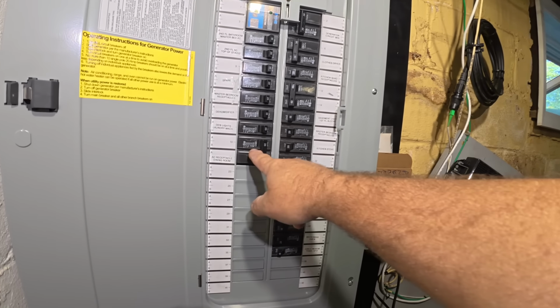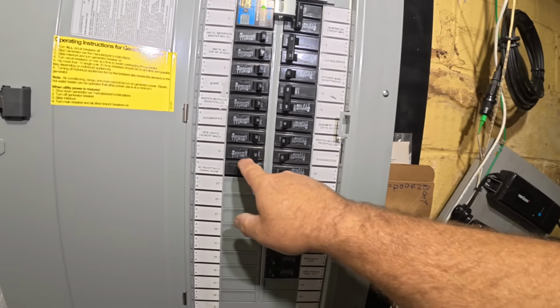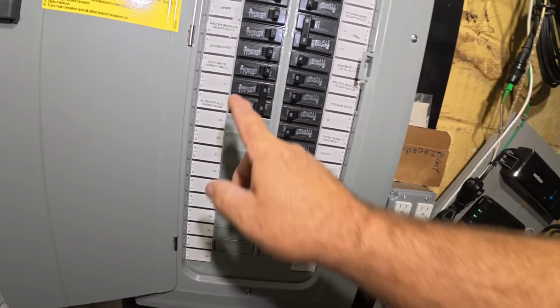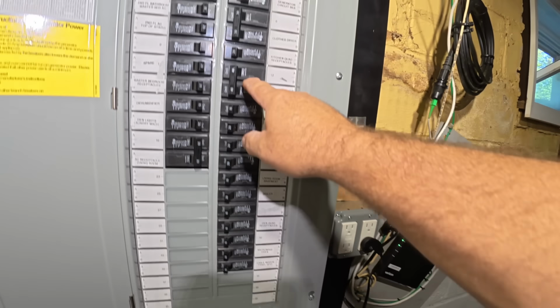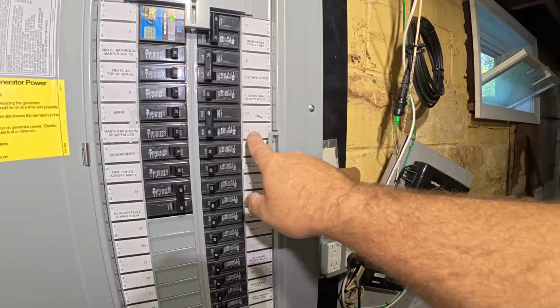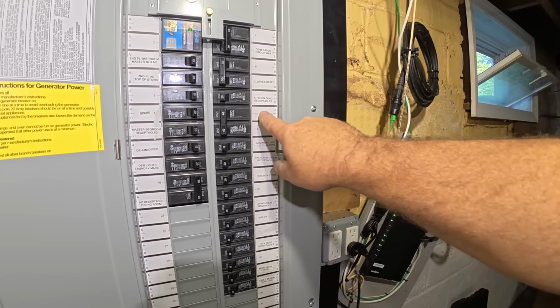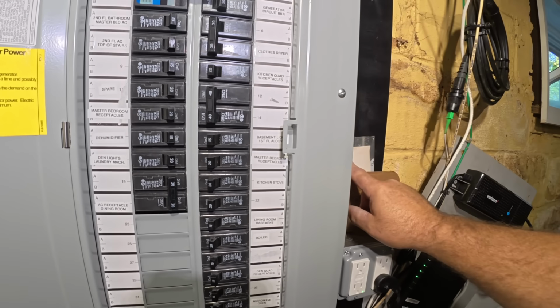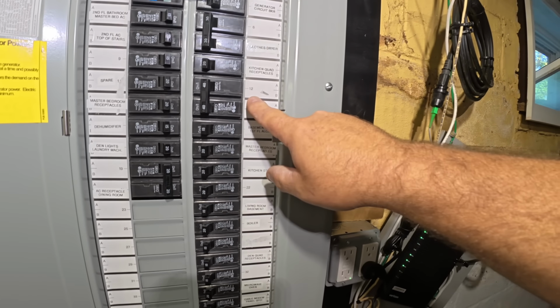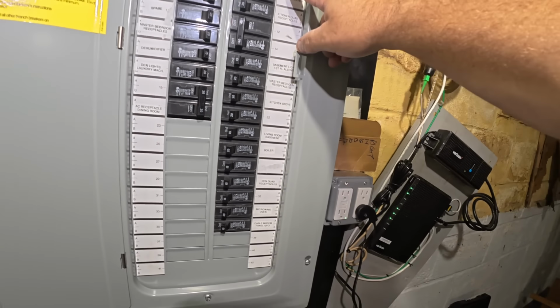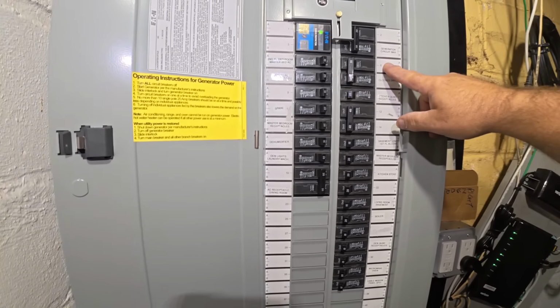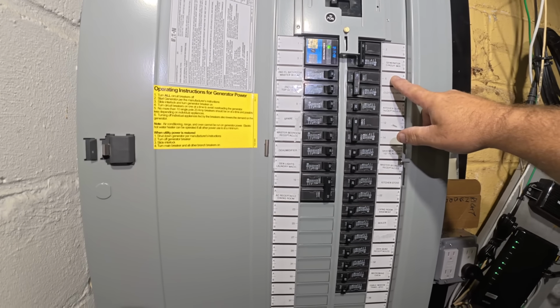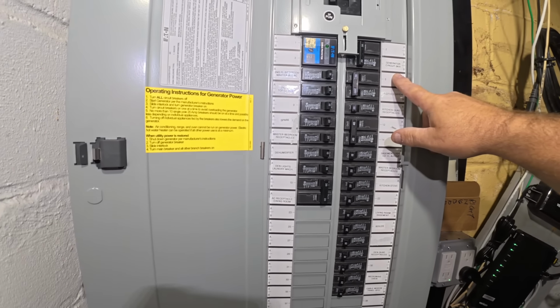I think we're going to change this though to a single pole receptacle at some point, or a 120 volt circuit rather. So really, this double pole 40 I think was repurposed in the kitchen. That's what it said on this. It was disconnected, but now you can reuse it. And of course the clothes dryer will be marked with the orange labels so that they know not to use this with the portable generator.